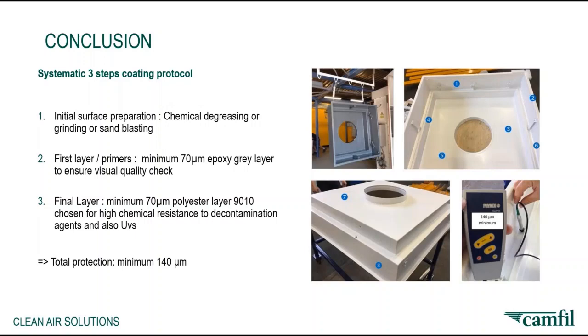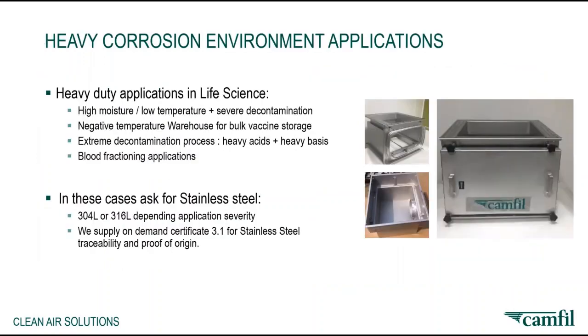Step 2 is a first layer, also called primer, with a minimum of 70 micron gray epoxy layer to ensure a first visual quality check. Many primers are epoxy-based and show excellent corrosion resistance and adhesion strength. They are used as a pre-coat underneath other paint types. Step 3, the final layer, will be a minimum of 70 micron polyester layer chosen for high chemical resistance to decont agent and also UV resistant. The total protection will be 140 micron.